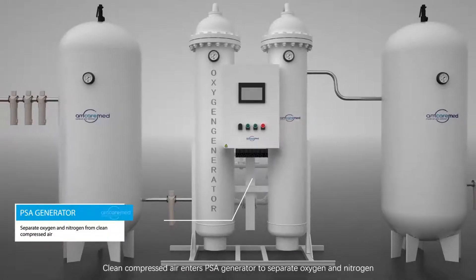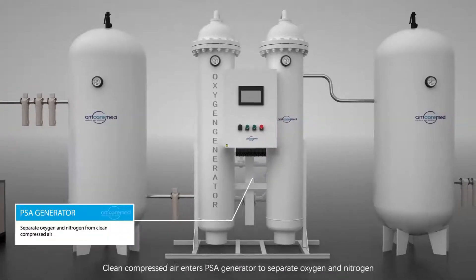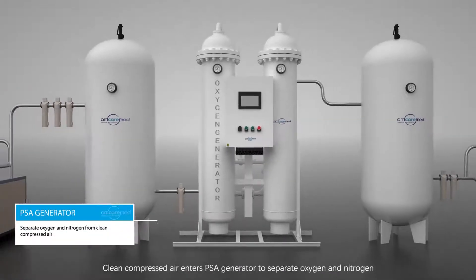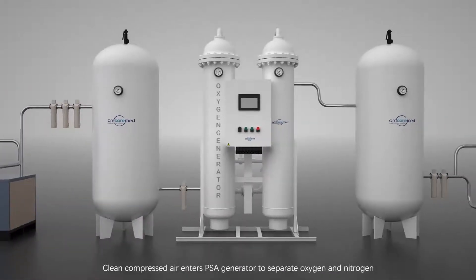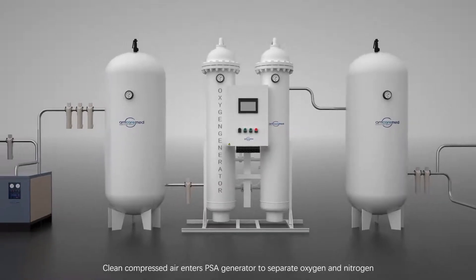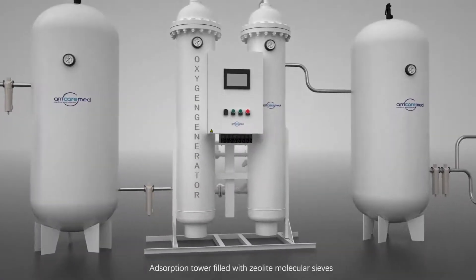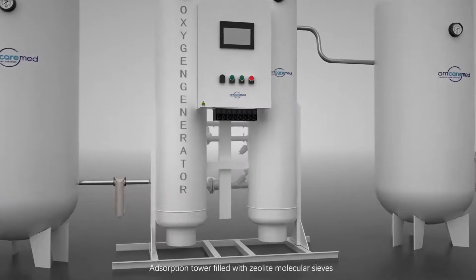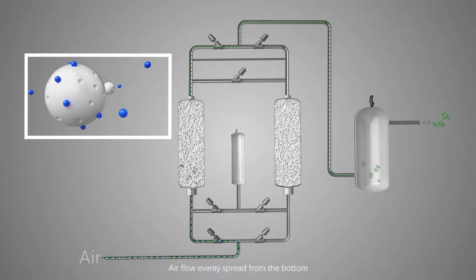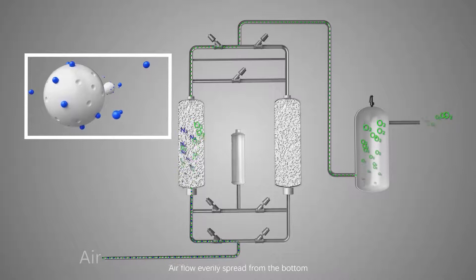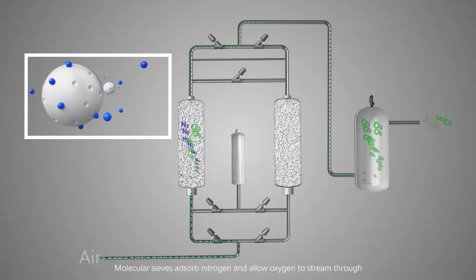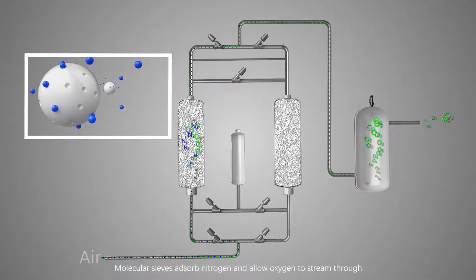Clean compressed air enters the PSA generator to separate oxygen and nitrogen. The adsorption tower is filled with zeolite molecular sieves. Air flow spreads evenly from the bottom, and the molecular sieves adsorb nitrogen, allowing oxygen to stream through.